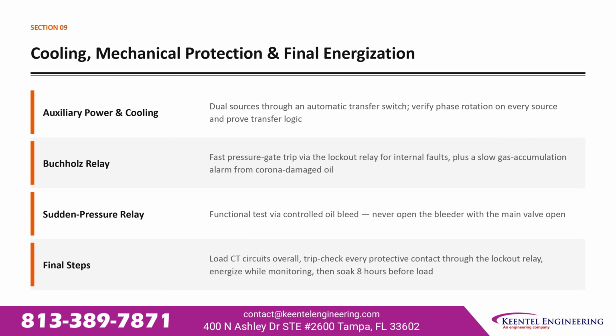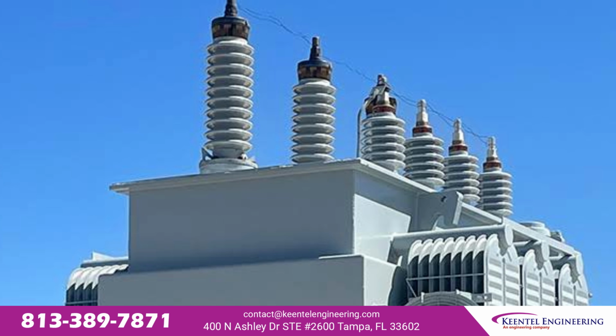The sudden pressure relay gets a functional test through a controlled oil bleed. Never open the bleeder with the main valve open. For final steps, load the CT circuits overall, trip check every protective contact through the lockout relay, energize while monitoring, then soak for 8 hours before adding load.